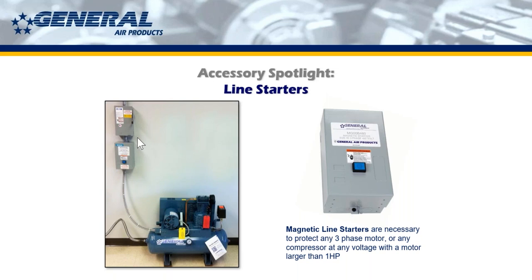So oftentimes in the field, these things become a problem. I can tell you that it's about a one-day turnaround on them. And again, if you know you want or need one, when you put in your order for the compressor, you need to include the information about the voltage that the unit is being wired for. They are voltage specific.